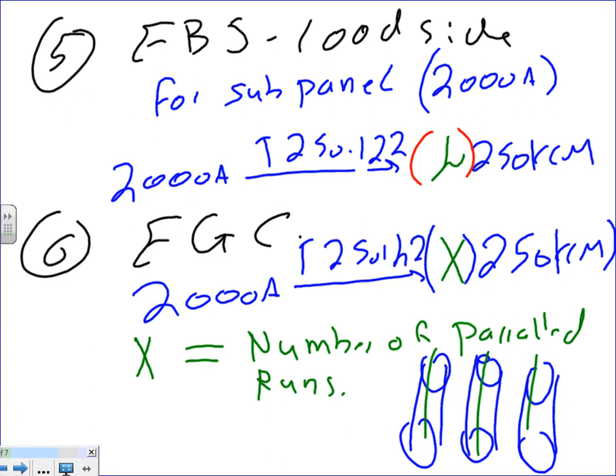Can you guys see that 5 and 6 are identical, except for 5 you only need 1? You really only need to bond one side of the conduit. It's a good idea to bond both sides, but you can bond only one side of the conduit, especially if you're using an equipment grounding conductor. Any question about number 5 and 6 before we move into number 7 and 8?